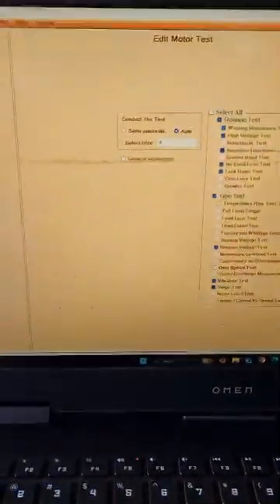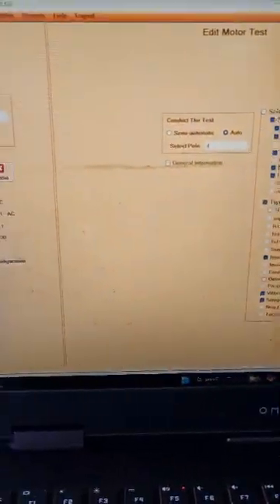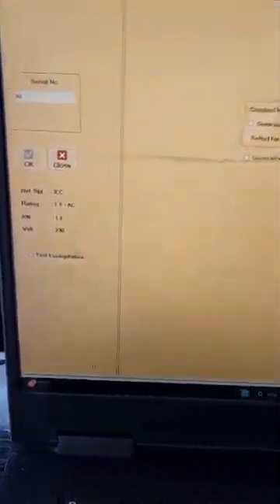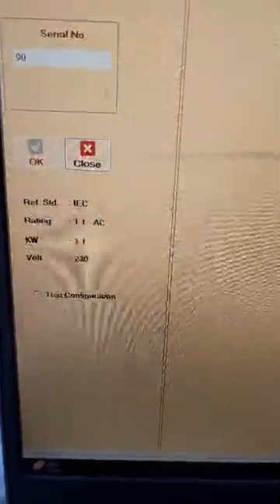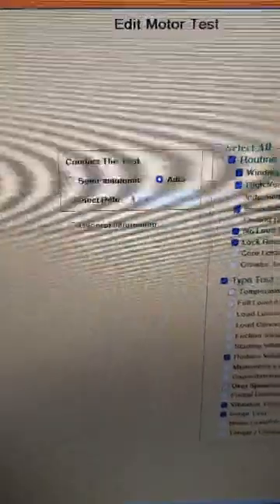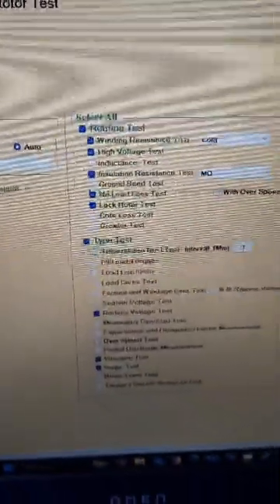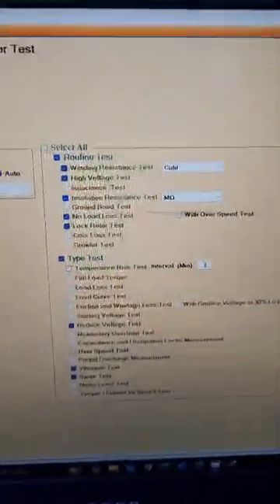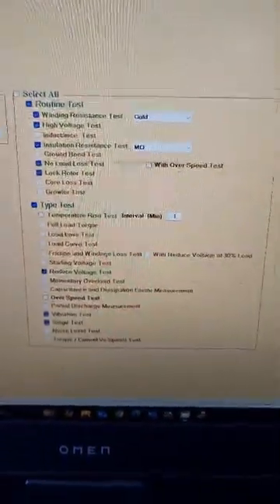Let me first explain this. This is a motor test. The serial number you can see is 90. This is complying with the reference standard IEC. The rating of the motor being tested is 1.1 kilowatt, and it's rated for the voltage 230. And here it works in both the modes, semi-automatic as well as automatic mode. And what we are demonstrating here is the automatic mode in which this particular motor will be tested.